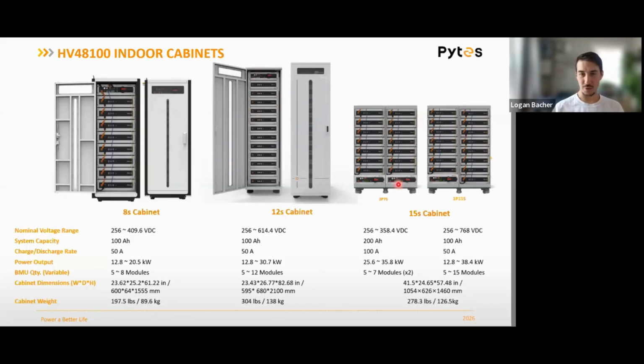But again, indoor only. And I also want to make a point here that none of these have any kind of fire suppression, fire detection, smoke detectors. These batteries do not have heating pads inside, there's no fans, there's no air conditioners. So when you're doing a design and you're looking at these, just make sure you have done your due diligence and you've confirmed with your AHJ exactly what they want to see. Because if you put these in and then later on you found out, oh, we actually need NFPA compliance, we need aerosol suppression, we need a sprinkler system, et cetera - none of these solutions have that.